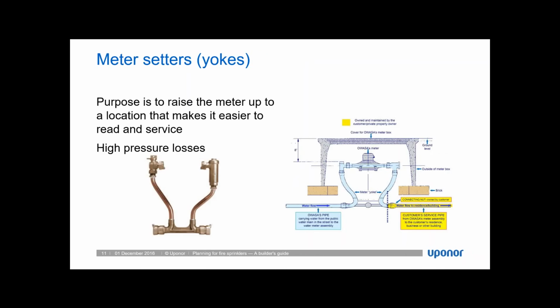Another component that is often overlooked when the initial sprinkler design is being considered is a meter setter, or sometimes it's called a meter yoke. Now, this is a device that's typically used to raise the meter up into a location, making it easier to read and easier to service. Sometimes it's in a meter box that can then be accessed more easily by the meter reader. You can see here an example of that meter yoke lifting the meter up into a box in the ground. The issue with these meter yokes is that they often have very high pressure losses, and they're often not incorporated into the initial design. It's not something that people usually think about, or maybe they don't even realize that it's something that's going to be used.